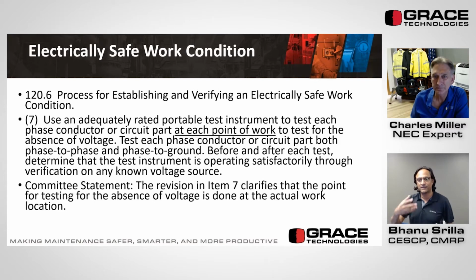So meaning if you connect our device or other devices in the same UL 1436 device, whenever you push a button or put a meter outside, it's going to verify where it's connected. For example, let's say it is on the load side. We verify that load side, make sure the de-energized state is verified using a 3-point test or an absence of voltage tester. You de-energize the system, absolutely good. At that juncture, you lock it out and then you open the panel. So if you put this at each point of work, then in my view, from the operator perspective, you still have to be suited up and verify at each point of work.